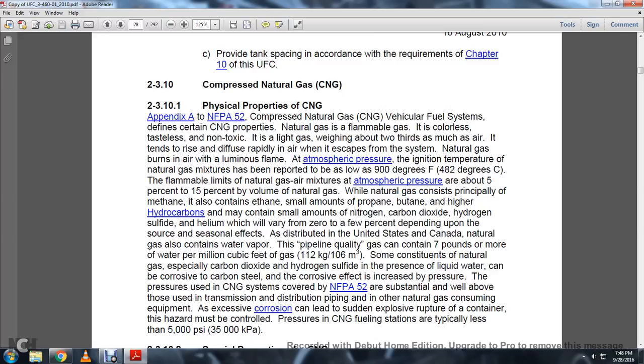The natural gas also contains water vapor. Pipeline quality gas contains 7 pounds or more of water per million cubic feet of gas. Constituents of the natural gas, especially carbon dioxide and hydrogen sulfide, with the presence of liquid water, can be corrosive to carbon steel. The effect increases with the pressure used in compressed natural gas systems covered by NFPA 52. The risk is substantial, well above that of transmission, distribution, piping, and other natural gas consuming equipment. Excessive corrosion can lead to sudden explosive rupture of the container, and the hazard must be controlled. Pressure at continuous compressed natural gas fueling stations is typically less than 5,000 psi.